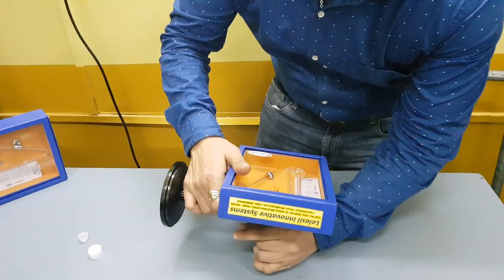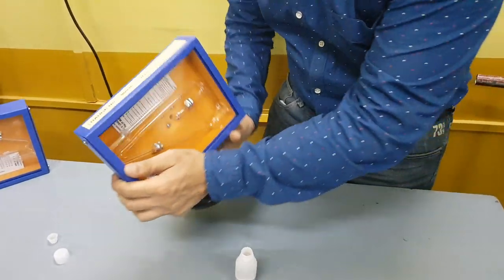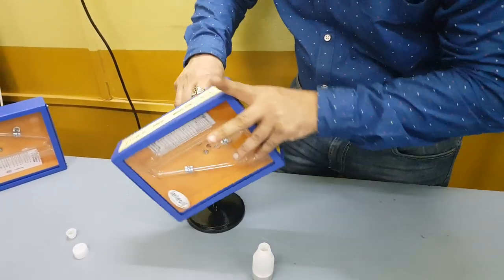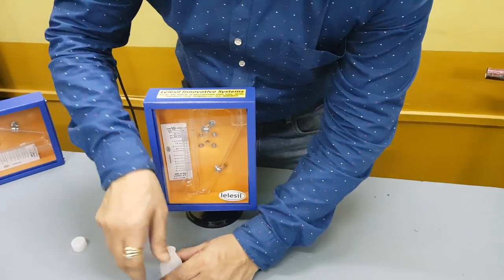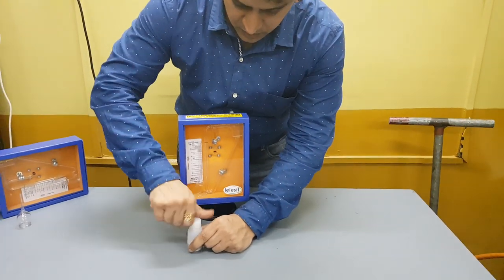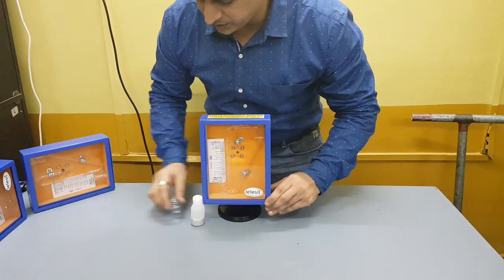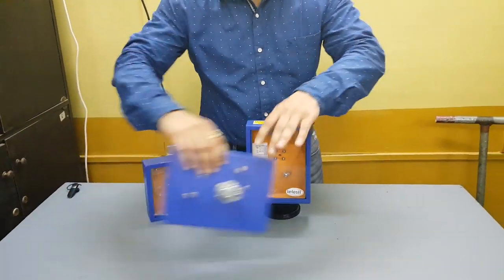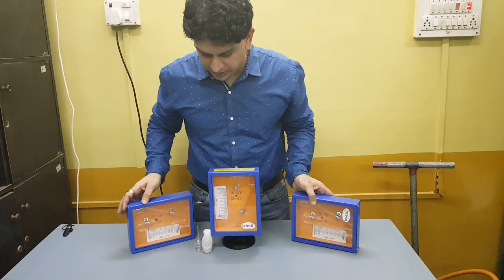Just lock it, mercury has been removed, the gauge is placed, tilt it and bring it to position zero. Once it is done, insert the cap. The complete system is done. Here you see two more gauges which are again McLeod gauges.